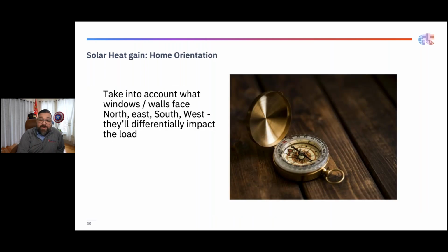Oh, don't forget about the orientation of the house. This is easy to fix in some software programs like Wrightsoft. I always forgot about this. One of the best things that happened to me was Google. You can just enter the address and Google Maps always pops up with north vertical, right? It's really easy to figure out afterwards. But typically, we just identify which direction the front door faces when we're doing a site survey so we can get the direction of all the walls right. So we understand the orientation as we're entering it, okay?